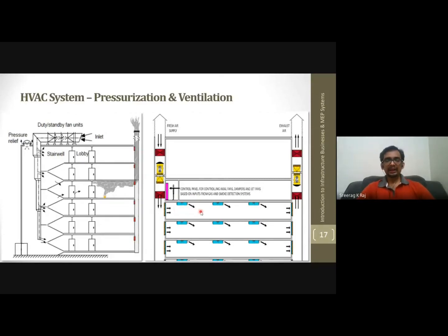So how this will work in the normal situation: based on the carbon dioxide sensor inputs, there will be a control panel that will sense the carbon dioxide level. We can set the level accordingly. These fans will supply the air to the basement area through a particular shaft or duct, and it will be connected through certain grills to the different floors, like different basements. And there will be some horizontal axial fans that will give circulation within the floor area. And there will be some exhaust fans also. So automatically there will be supply of air, and return air will be through exhaust fans. So there will be some movement here. That is called basement ventilation basically.